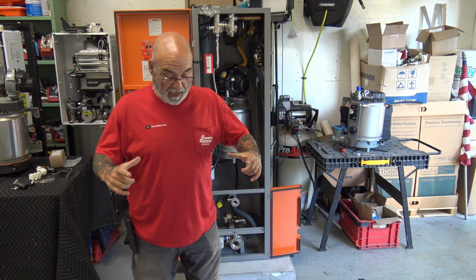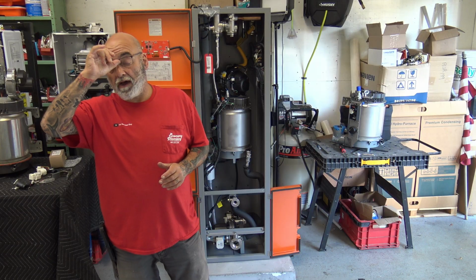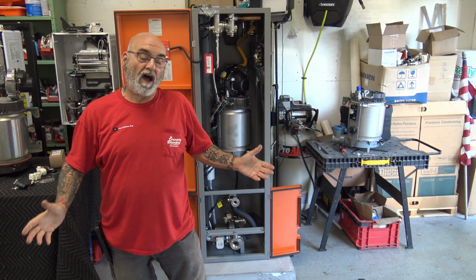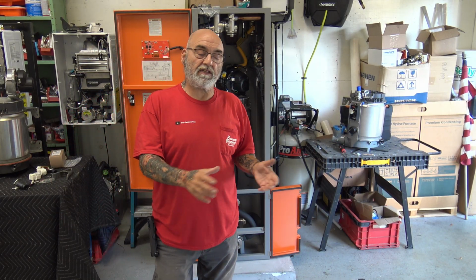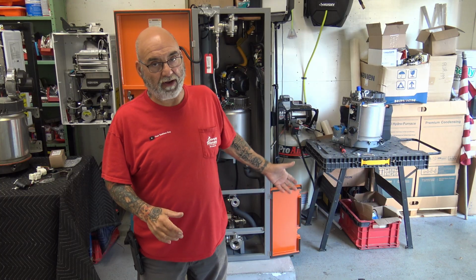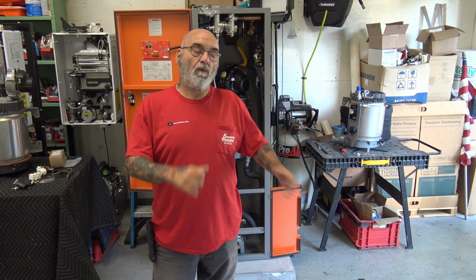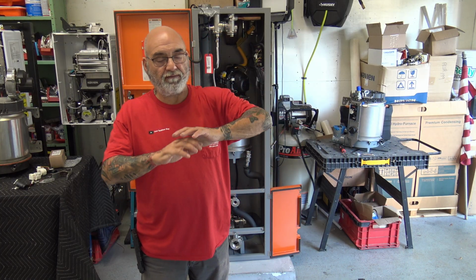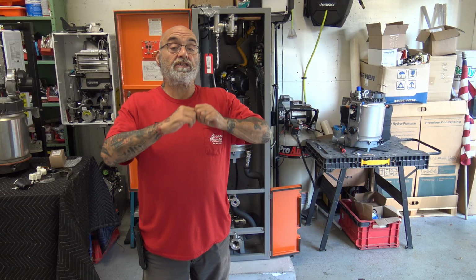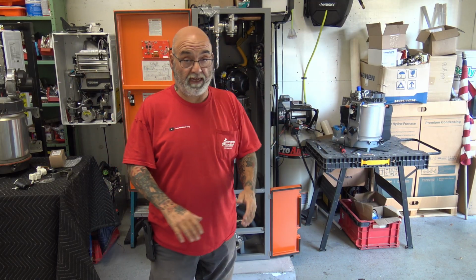So you need some type of thin pan, they make a moldable pan. I just bring a lot of rags and let the water come out onto the rags and then mop it up. There's nothing electric down there. And once you take the pressure down, pop the relief valve, there's no pressure on the system. So it's not going to spurt out and go all over the place.